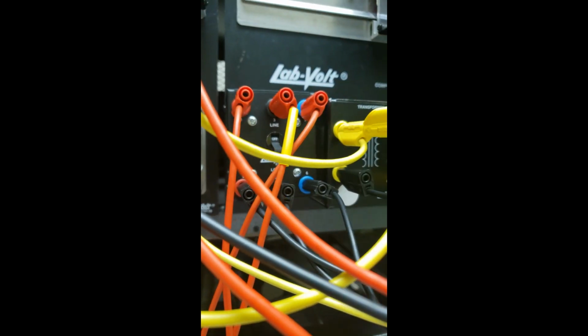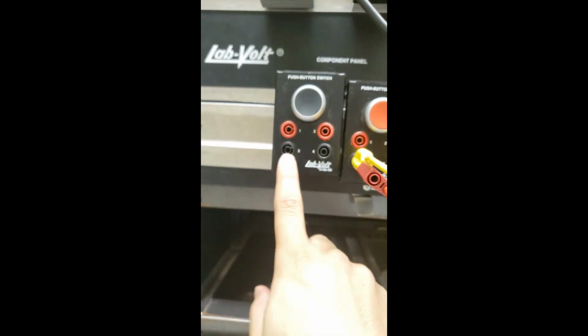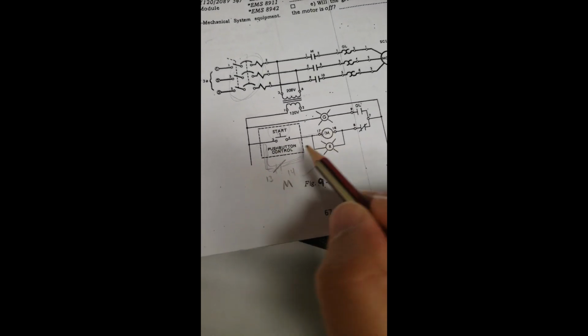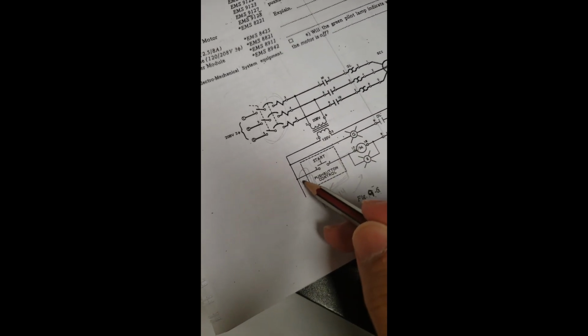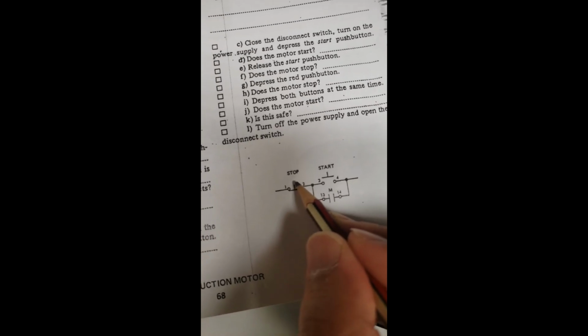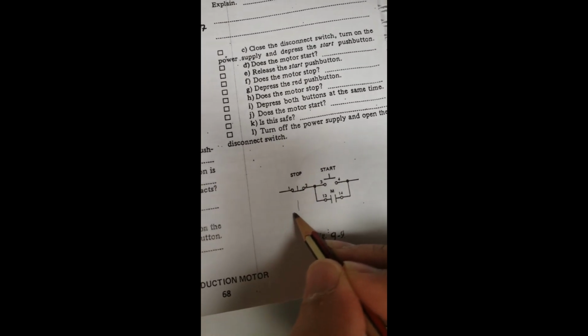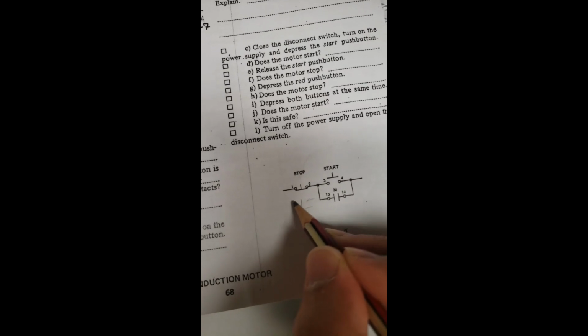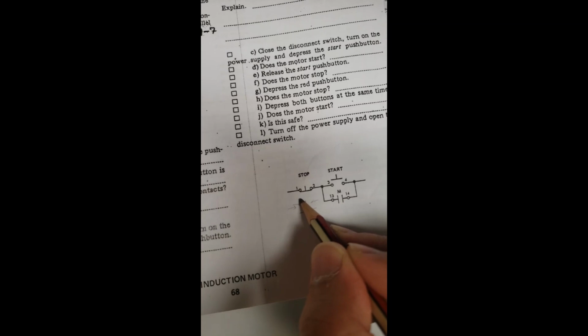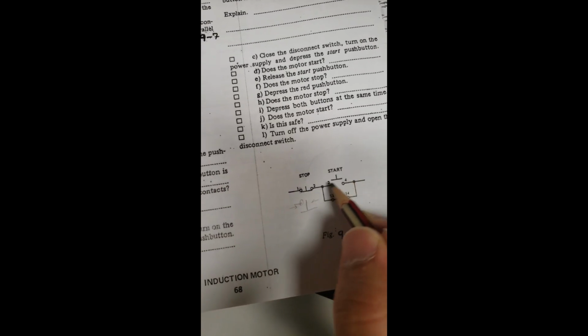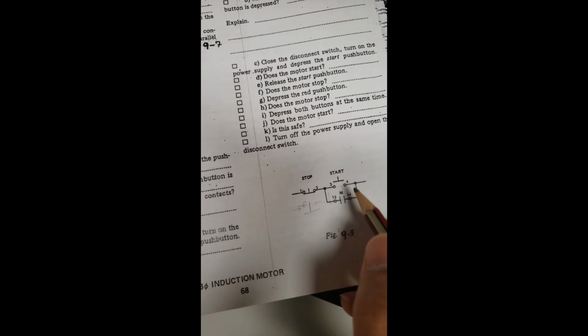There is no stop push button. We didn't use it. So in order to use it, if I want to stop the motor, I have to place the stop push button here before the holding contact. So the current will stop at the switch, like this one. So if I press the stop push button, it will become like this, and the current will stop here, will stop at this terminal, and it will not go through the coil or through the start push button.